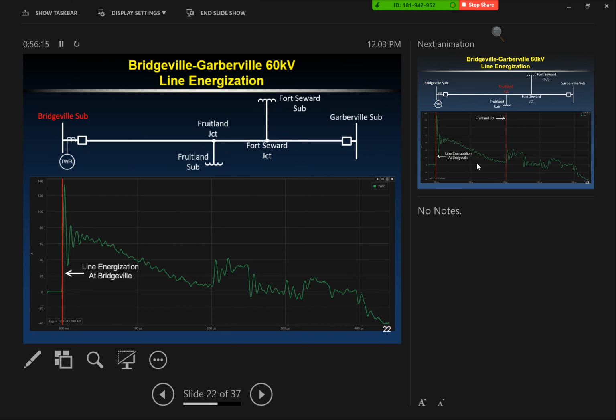So that's our line energization. We get this ringing effect - you see that a lot on traveling wave events. It's stuff going on the CT secondary, so it's just noise, we're not concerned about that. But we know we can map this out - we can calculate what distance looks like in terms of time on this waveform.